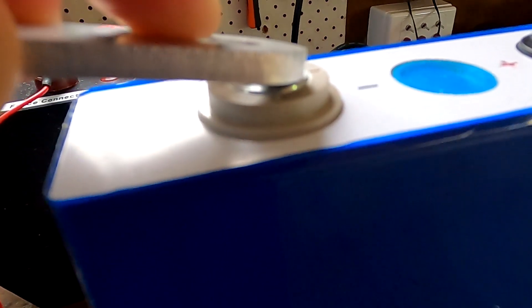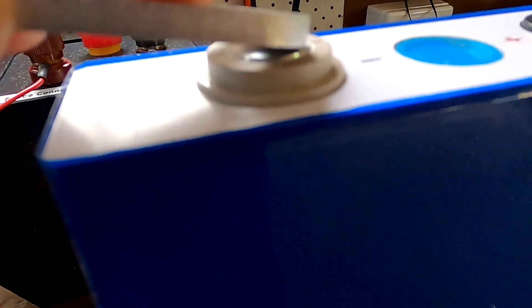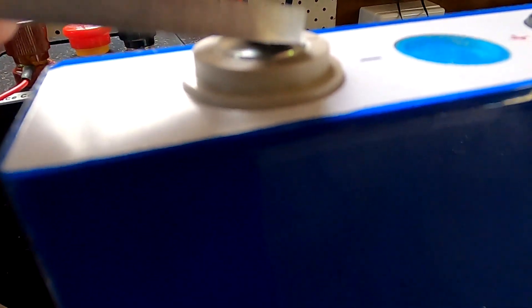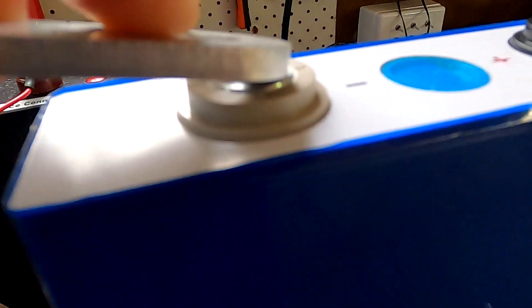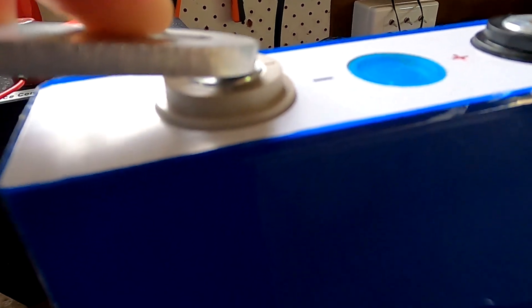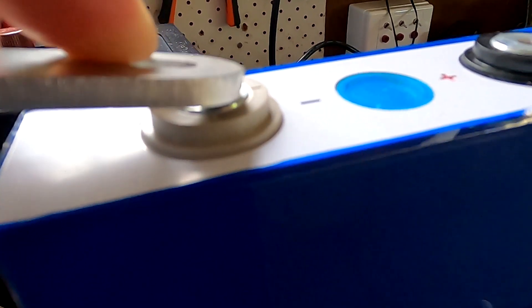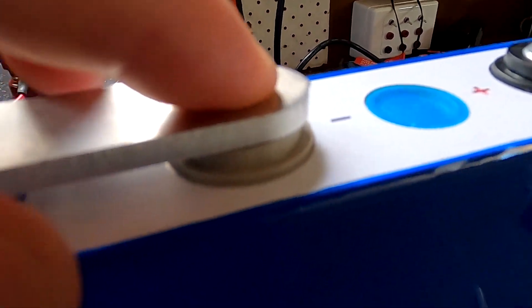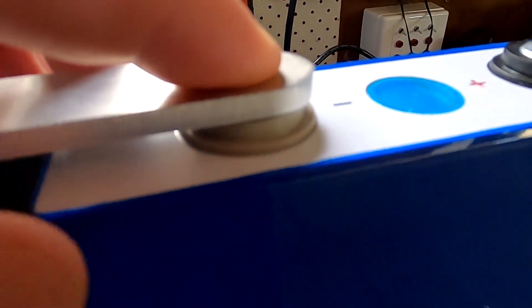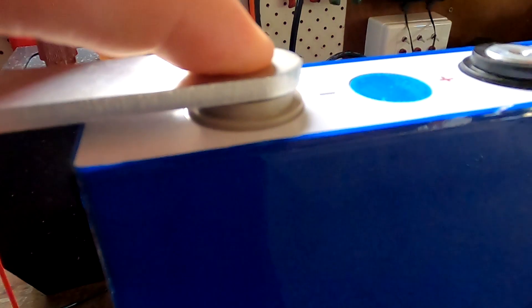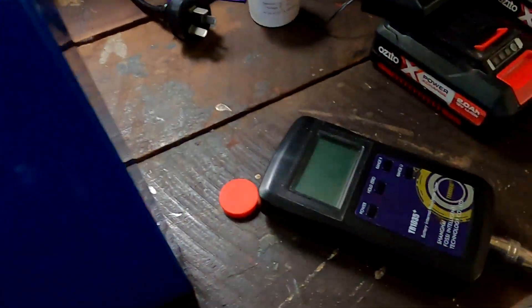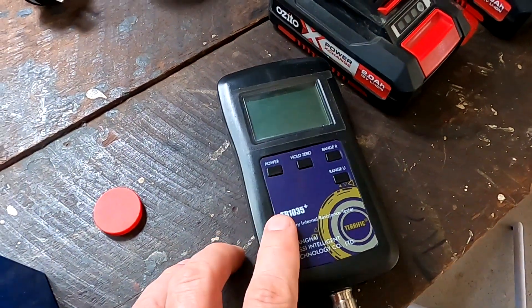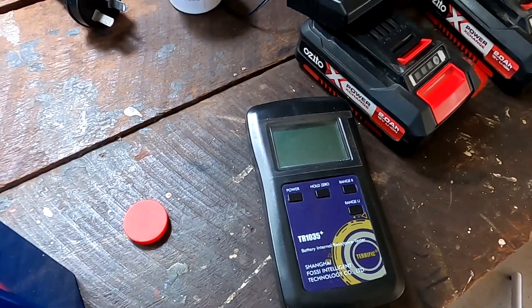So you cannot actually measure or qualify your connection with an internal resistance meter, because even though the resistance is very low, once you start pushing serious current through this one, the small connection area will of course heat up and cause the candle effect which we have seen in the previous video. So only a really flat surface, the contact area is important here for our high currents, and this is not something the internal resistance meter can actually measure. This was a good tip from you, but it didn't help solving the problem.